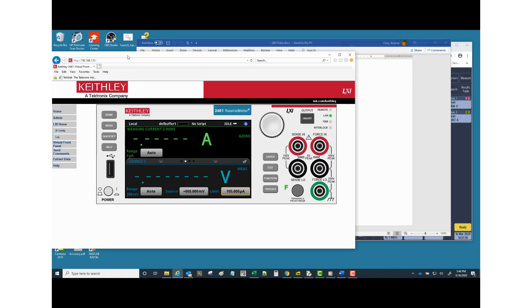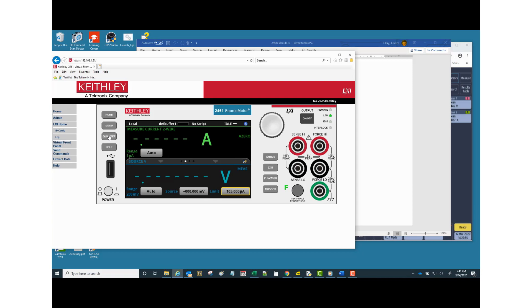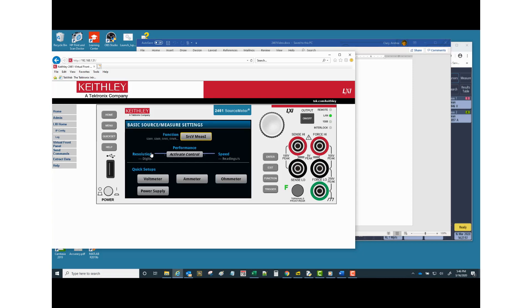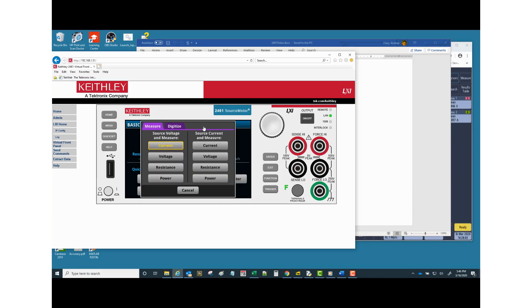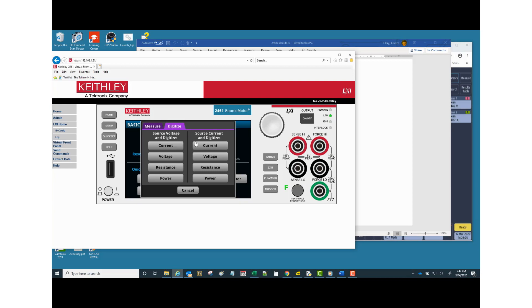So I want to talk a little bit about how do we do this 10 amp pulse and how do we get the measurements of the voltage that occur during that pulse? The 2461 has got two different types of A to D converter in it. So I'm in just power on default conditions right now. But if I hit this quick set button and then with the function here, click that. Okay, two different types of A to D converter. With the measure tab, this will be using the integrating A to D converter. But we are going to be doing pulse mode, so we need to be able to get our measurements quickly. So there are also a pair of one mega sample per second digitizing A to D's in here. So for this RDS on measurement, I'm going to source current and digitize the voltage.